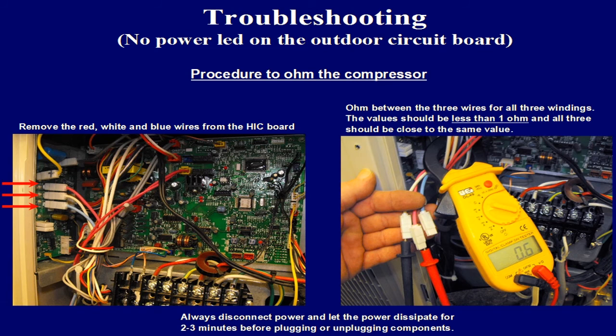When checking the winding resistance through the compressor, remove the red, white, and blue wire from the HIC board. The compressor will ohm out similar to a 3-phase motor and should have close to equal resistance between any 2 windings when conducting a continuity test.